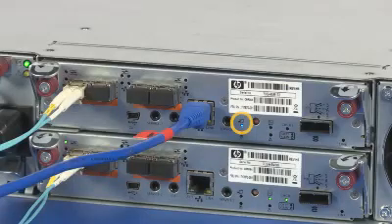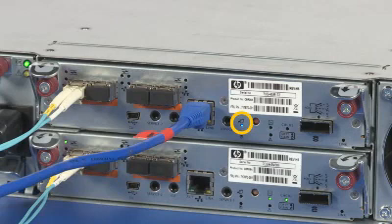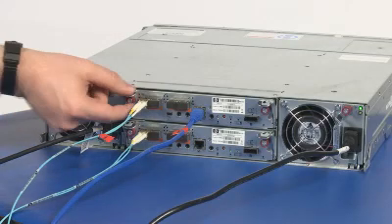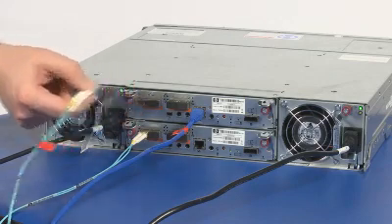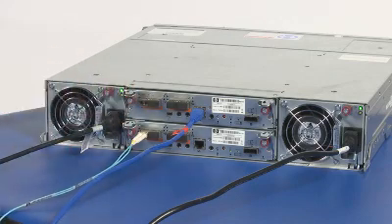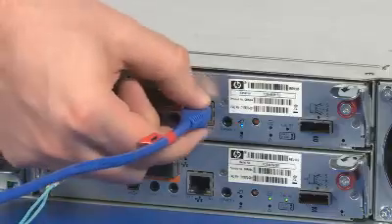The blue OK to remove LED on the controller illuminates, indicating that the controller can be safely removed. Locate the enclosure in which the controller module OK to remove LED is blue. Disconnect cables connected to the module. Label each cable to facilitate reconnection.